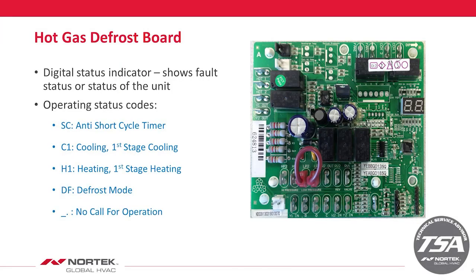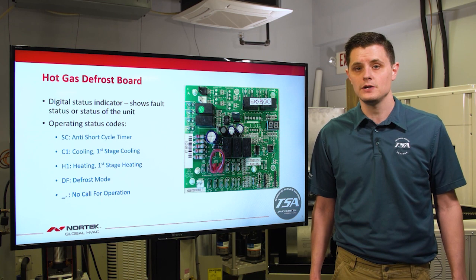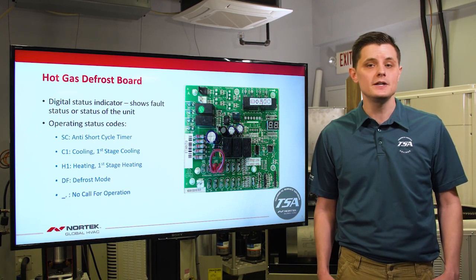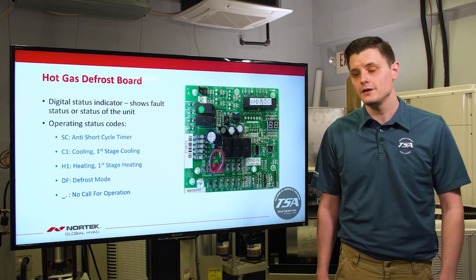SC will stand for your short cycle timer. C1 is your first stage cooling. H1 is going to be your first stage heat pump operation. Defrost mode will show DF, and if you see an exclamation point or a dash and a period on the digital, that just means you're in standby mode and ready for a call. On a two-stage unit you will also have a C2 and an H2 to indicate second stage.